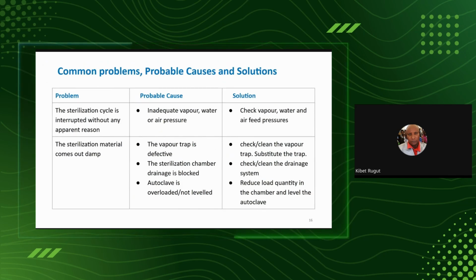Another problem that comes is the sterilization cycle keeps breaking or gets interrupted. Well, what could you do? You realize that it could be inadequate vapor or steam or water or air pressure. So maybe halfway through the cycle, the pressure for the door lock is compromised. For safety purposes, the sterilization has to stop until you sort it out. So those are the things that keep coming.